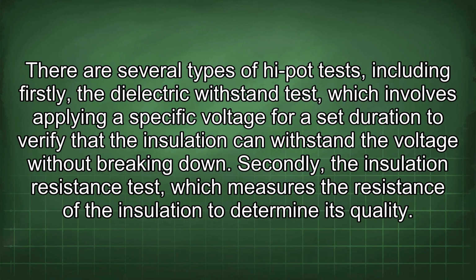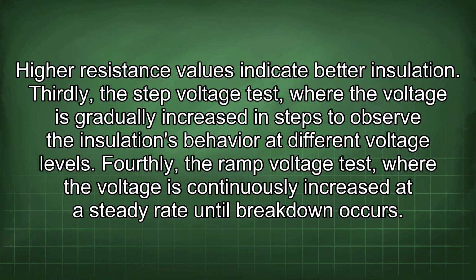There are several types of high-pot tests, including firstly the dielectric withstand test, which involves applying a specific voltage for a set duration to verify that the insulation can withstand the voltage without breaking down. Secondly, the insulation resistance test, which measures the resistance of the insulation to determine its quality. Higher resistance values indicate better insulation. Thirdly, the step voltage test, where the voltage is gradually increased in steps to observe the insulation's behavior at different voltage levels.